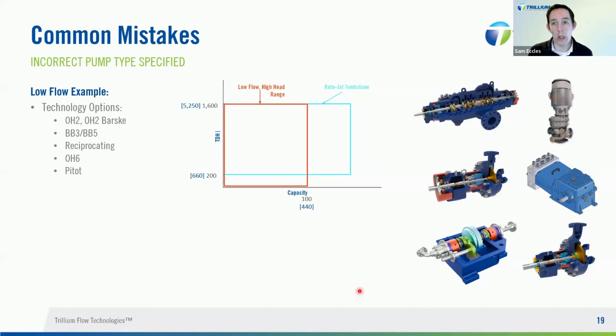We're going to talk about this section of the market that we're calling the low flow, high head range. This is really the size where there's a lot of volume in the market, generally lower cost units within this performance envelope, but it's where they don't get a lot of scrutiny. As an individual pump, it's not that significant. As a collection of pumps on a site, it becomes hugely significant. And by overlooking all of those, they very quickly become problem pumps. When we go out as our service group, it's very often pumps that fall into this performance window that we're being asked to troubleshoot.